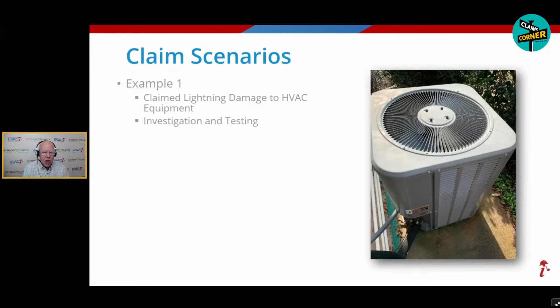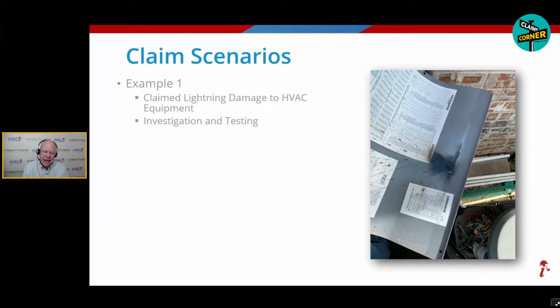System 2, we're looking at it. The first thing that happens is we open it up to check the electronics, and we see this big arc mark. Remember we were talking about arcing? And this is on something that's not connected directly to a wire, so we had some big energy here. If you put this panel back where it would go, look what's right there.